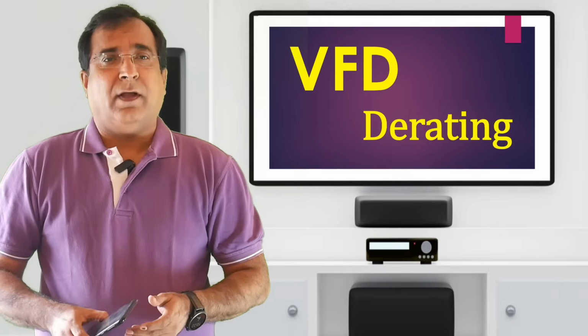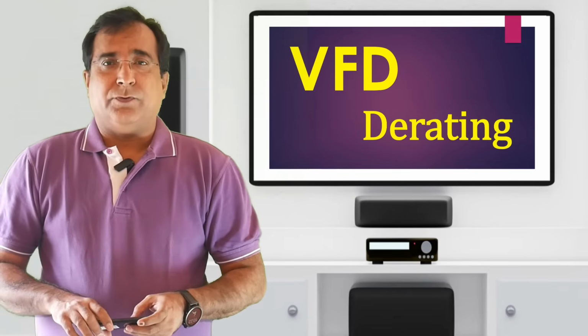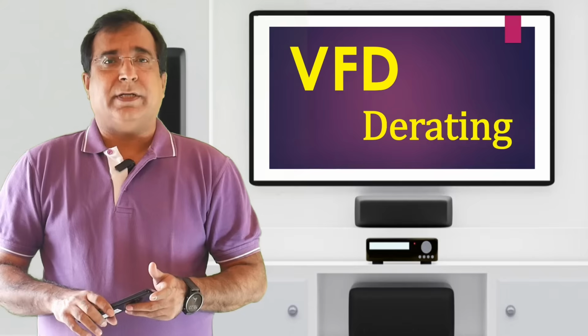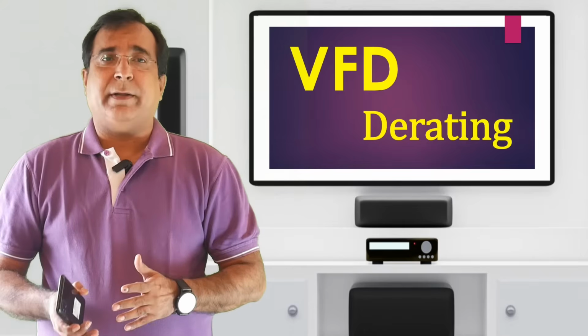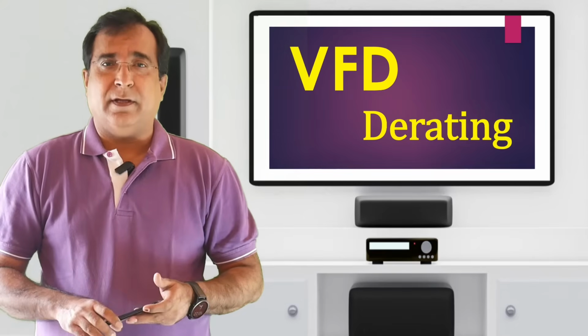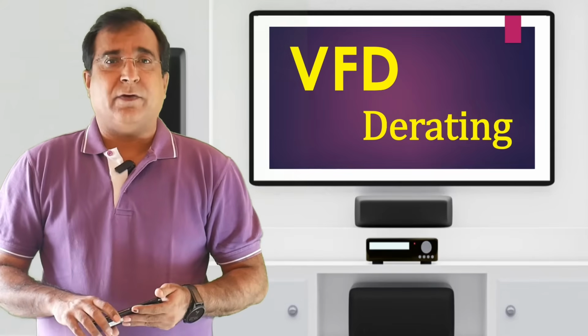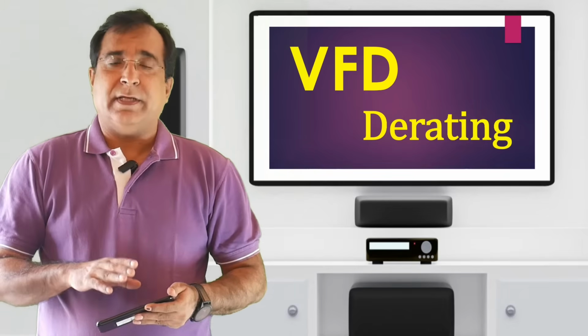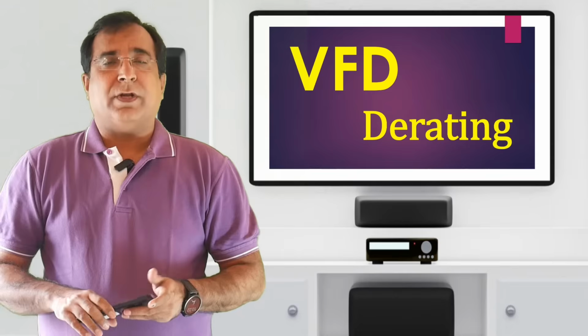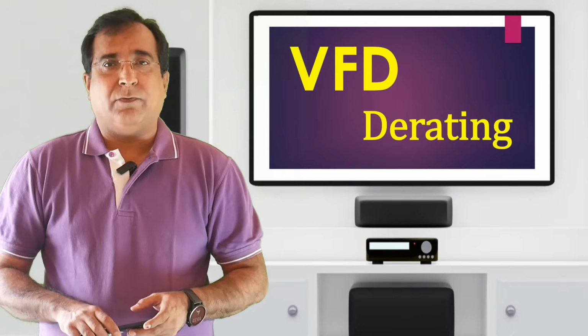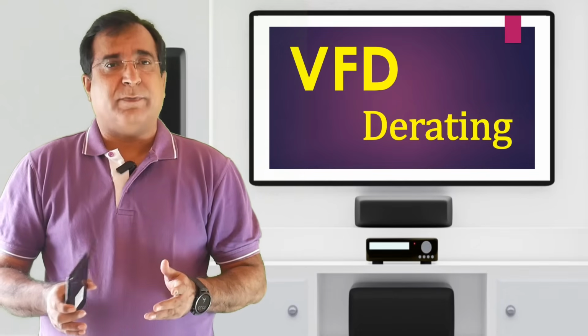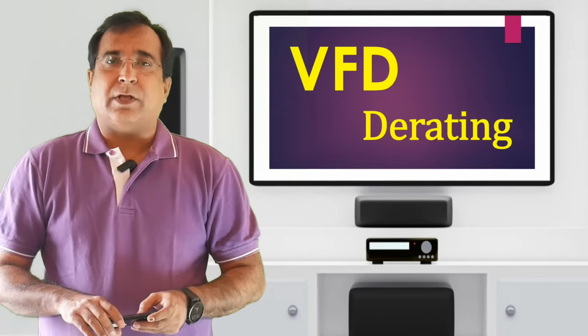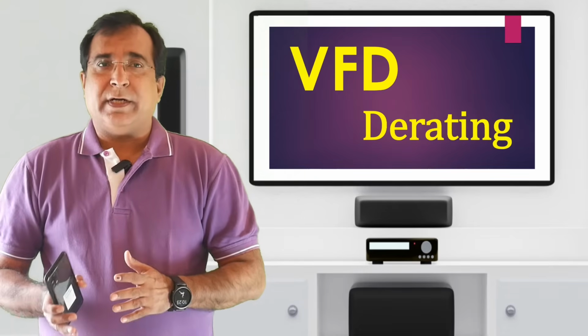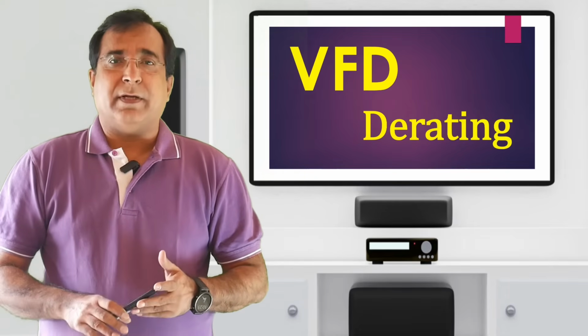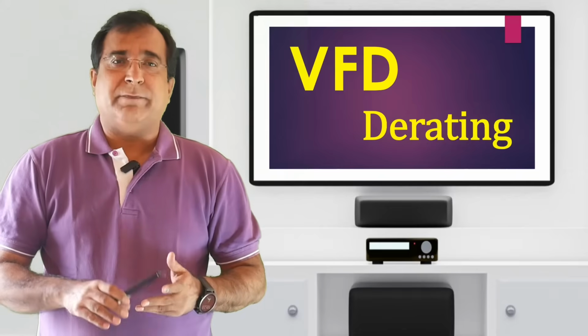Let's move ahead. VFD derating becomes an issue when you are setting up a plant above 3300 feet and when the ambient temperature is above 40 degrees Celsius. But you specify the current rating of VFD as per motor load requirement at the time of procurement. For example, you need to specify VFD for, suppose, a 200 HP motor at an altitude of 6000 feet. For a 200 HP motor, you need 230 ampere as current output of the VFD.